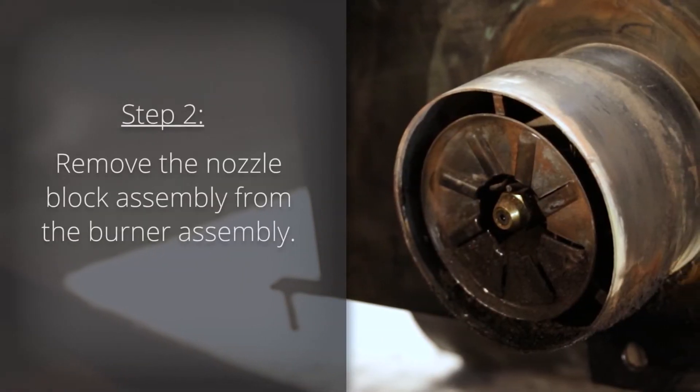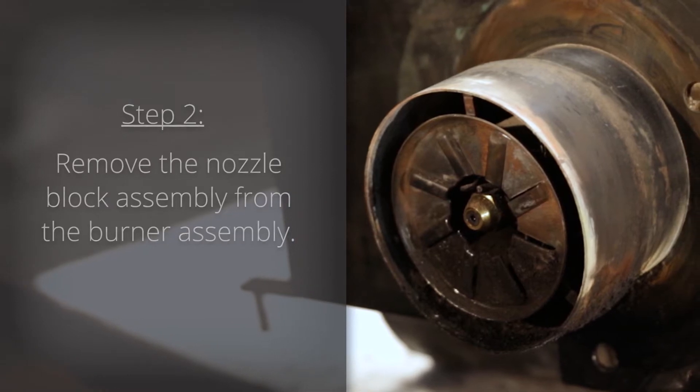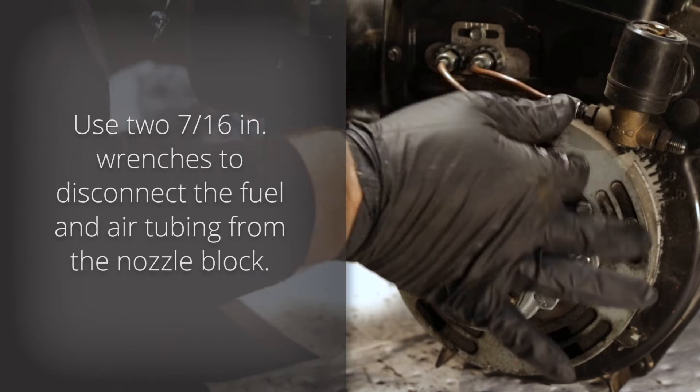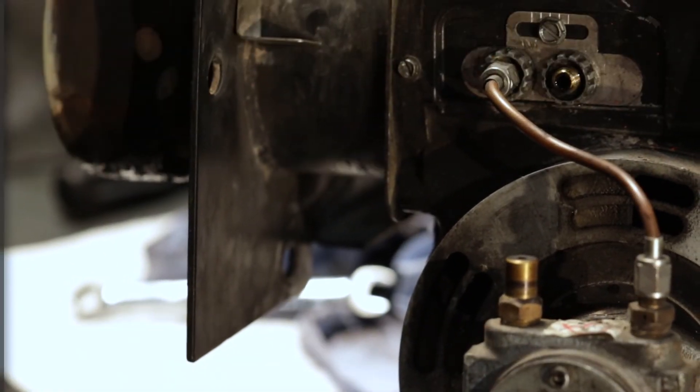Step 2. Remove the nozzle block assembly from the burner assembly. Use two 7-16th inch wrenches to disconnect the fuel and air tubing from the nozzle block. Once removed, clean and inspect the copper tubing. Replace as needed.